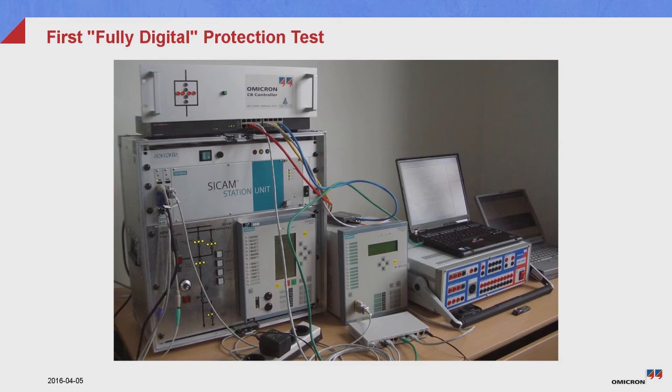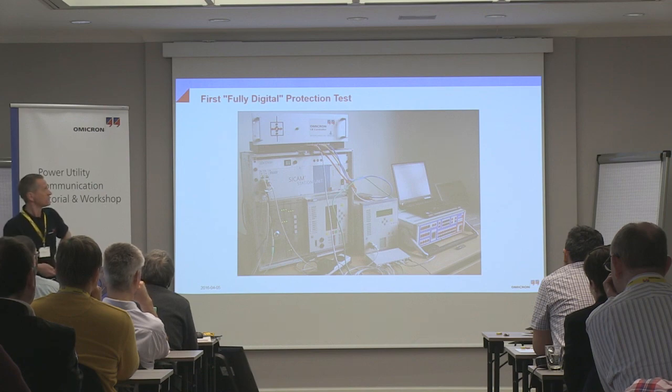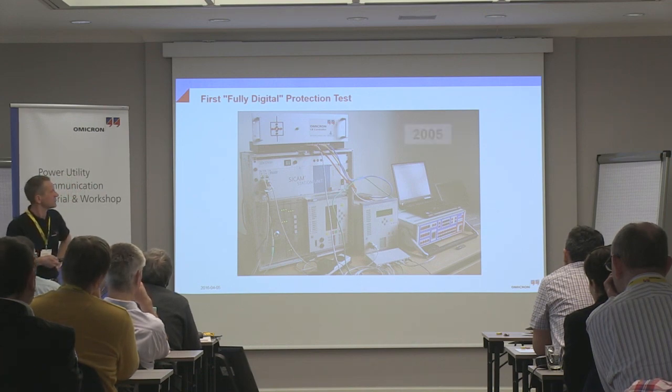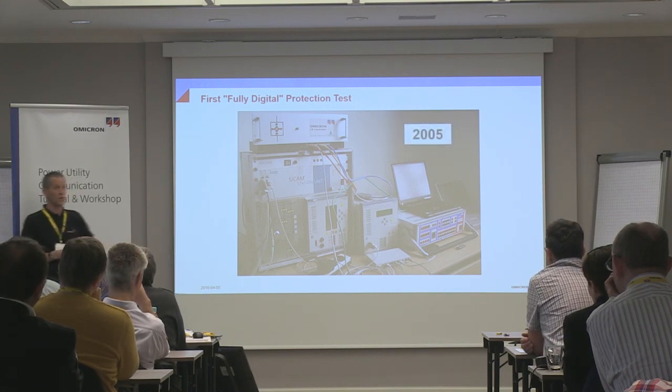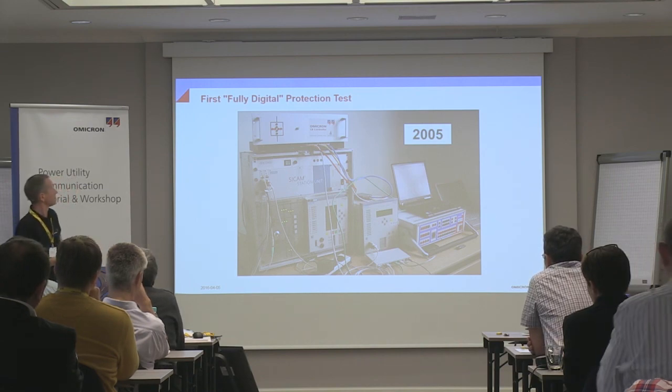This is a complete protection test. Do you see something that hits your eye on this complete protection test? Okay, to make it short, I only have 30 seconds. There is nothing connected here to the banana plugs. This was the first fully sampled values and GOOSE protection test, and it was in September 2005. It's more than 10 years ago. I can't understand why this is not in every substation today.